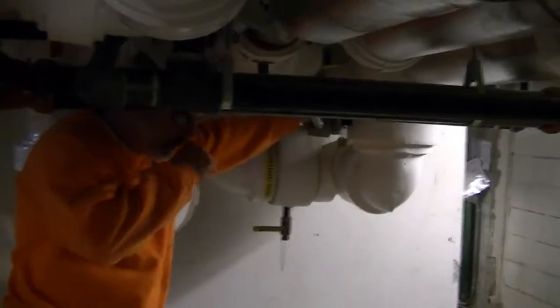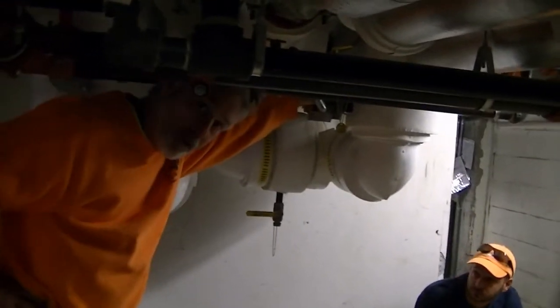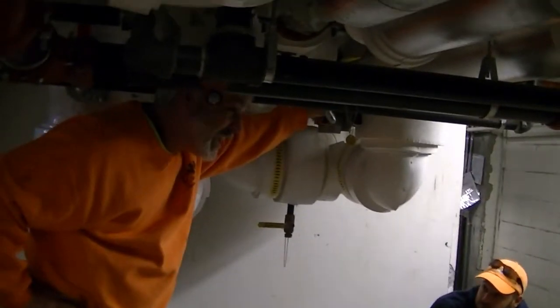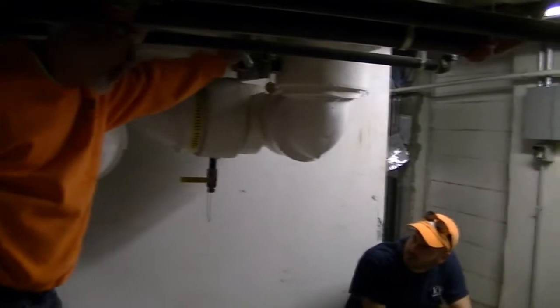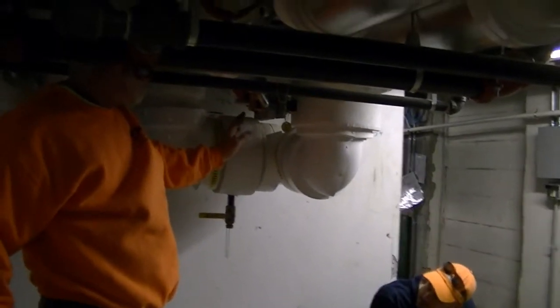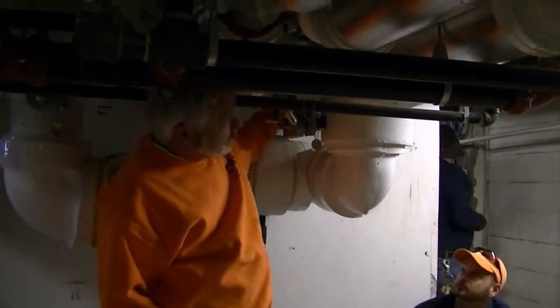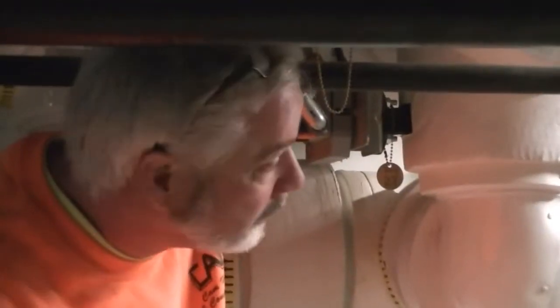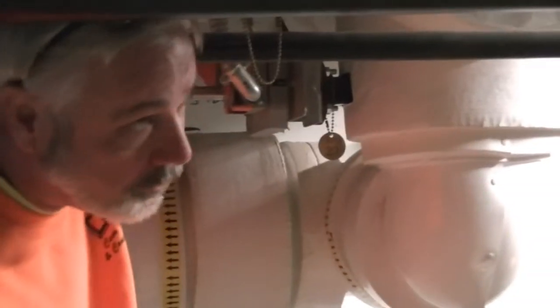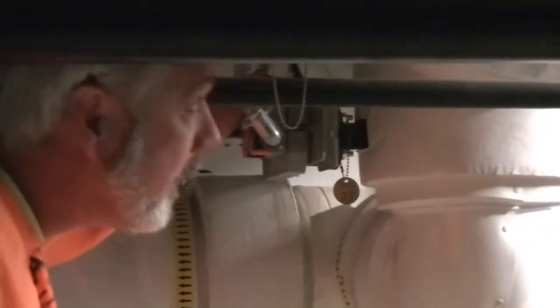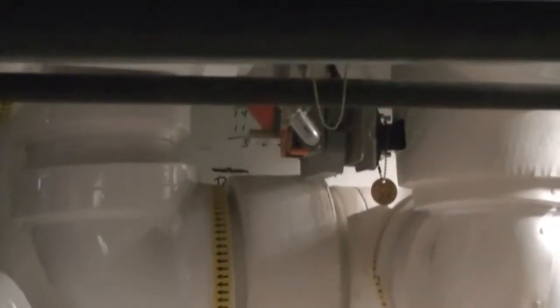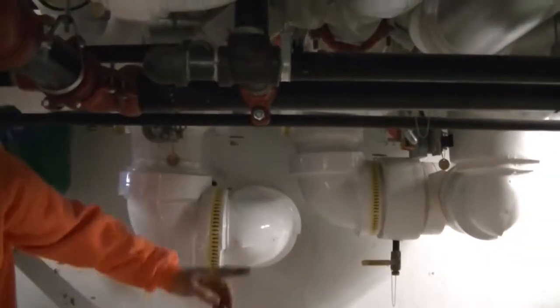No? Controls going up. The reset water temperature for the heating system in the building. This doesn't do anything with the domestic hot water. Okay? You have a branch valve and the main valve, and one tracks the other. Whatever one's doing, the other's doing the opposite. So if this one's closing, this one's opening. If this one's opening, this one's closing. Okay? And again, it's based off of the mixed water temperature that's leaving this valve.